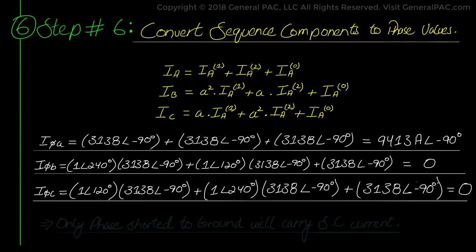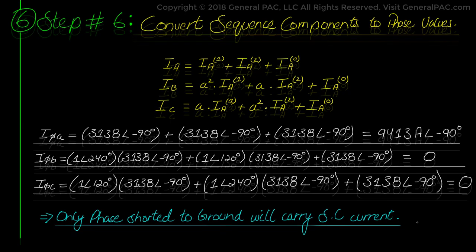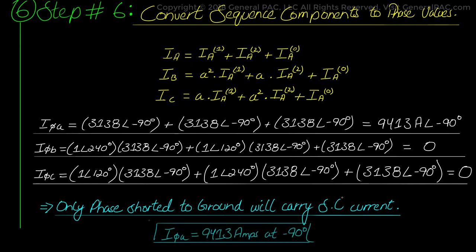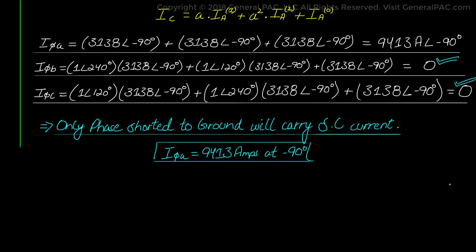Intuitively, only the phase shorted to ground is supposed to carry the short circuit current. In this case, the faulted phase is phase A, which has 9413 amps at -90 degrees. The remaining phases — phase B and phase C — have no fault current flowing, therefore they are 0.